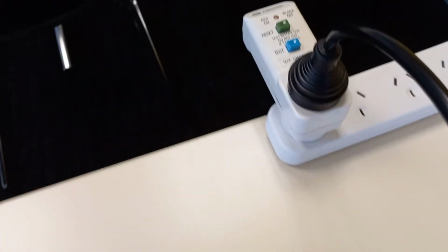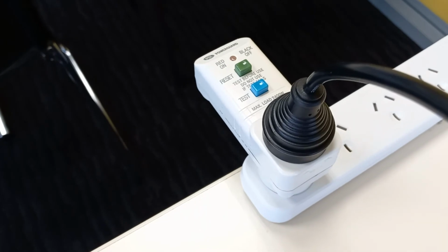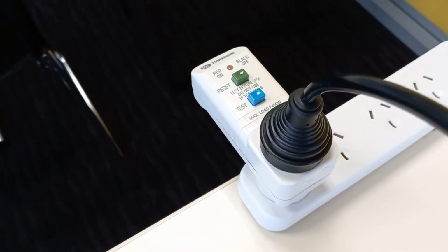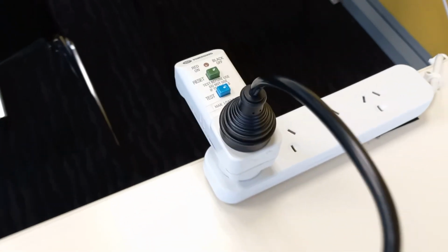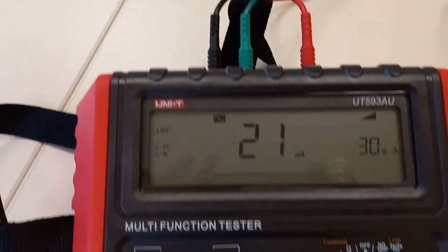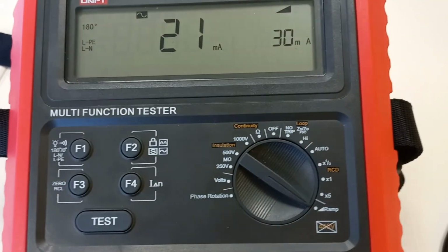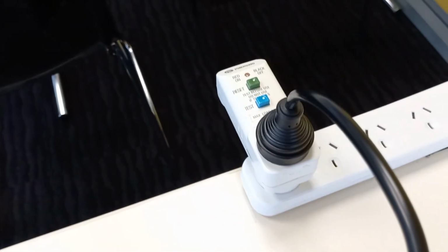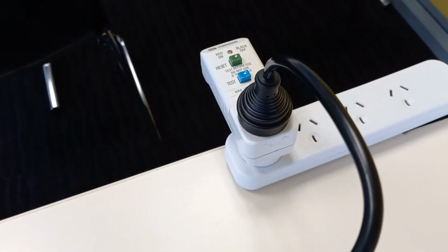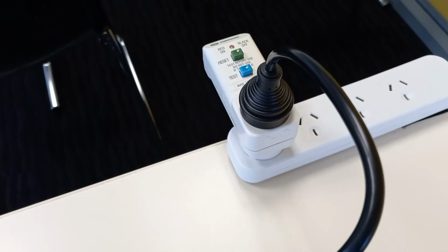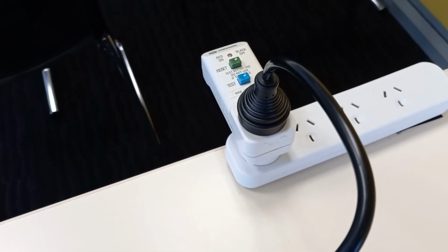If you're thinking about doing a higher level of testing of an RCD other than just pressing the test button, the same tests would be carried out for an RCCB or an RCBO that may be switchboard mounted. We would just plug the multifunction tester into the socket outlet of that particular circuit and carry out the same tests.